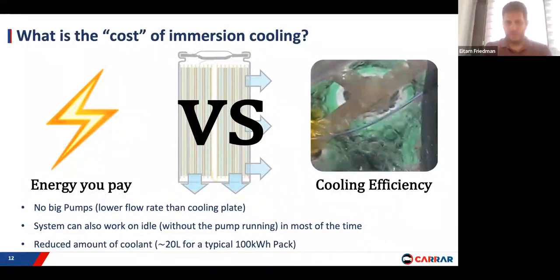The Carrar system relies on latent heat, not specific heat. Therefore, we don't need to circulate a lot of refrigerant to manage the temperature difference between inlet and outlet in the battery use case. Because we're using pool boiling, all of the heat energy from the cell goes to the phase change, so we need to circulate a very low amount of refrigerant - the flow rate is very low. As a rule of thumb, if other solutions need around 10 liters per minute, we require only 1 liter per minute, and we're able to dissipate more heat. So the pumps are smaller, power consumption is lower, and we reduce the parasitic energy needed to cool the batteries, also at high ambient temperatures.